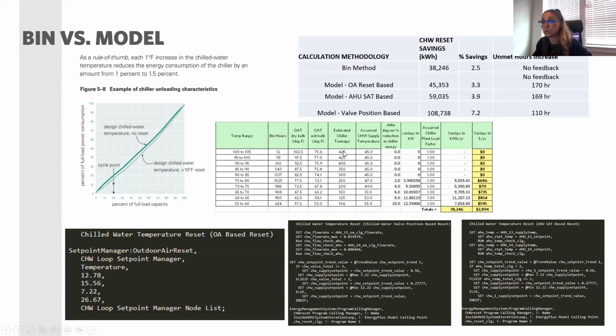But obviously, with bin or without bin, when you use outside air as the changing parameter, there's no feedback from the building. Especially since we know we are already sacrificing the unmet hours when we are raising the chill water temperature, we want to see what the maximum is. I guess we all know ASHRAE requires 300 for the maximum unmet hours that a building should have. So there's no feedback loop.